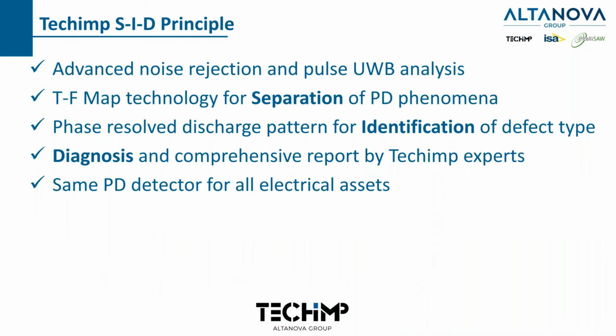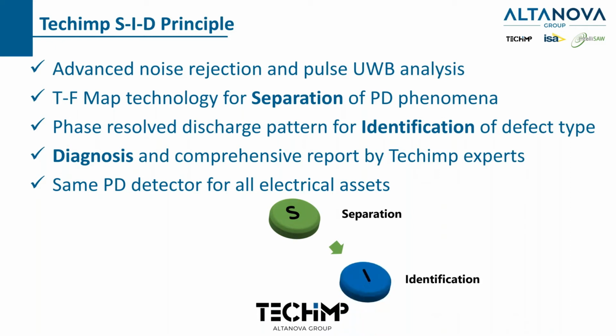So here's a graphic of what I just explained. Basically, we'll go in and we'll place a sensor or an antenna on the cable or the asset. It will pick up those RF signals. The software actually separates the different sources, including the stuff we don't want to look at, and it will identify the type of PD, whether it be internal or tracking. And then once we identify the source and the type, we can then diagnose the problem. So we can't diagnose a problem without identifying the source and the type of PD.